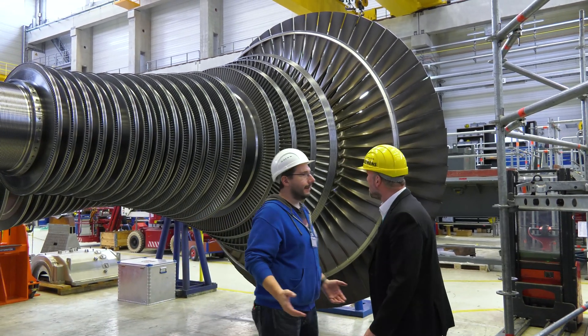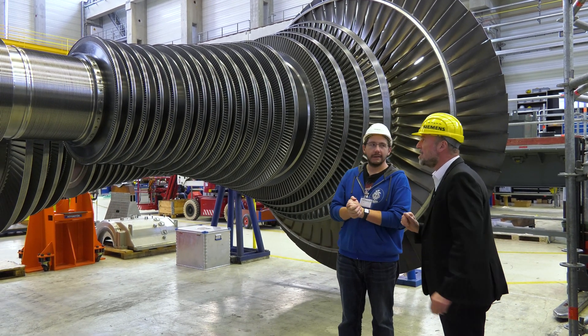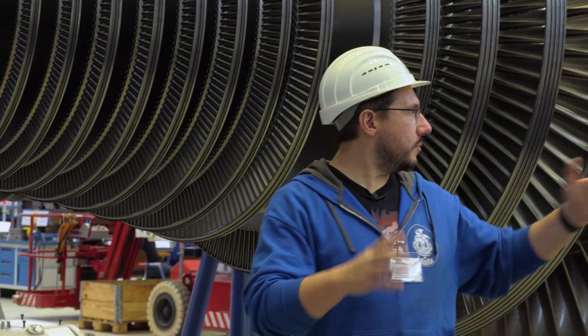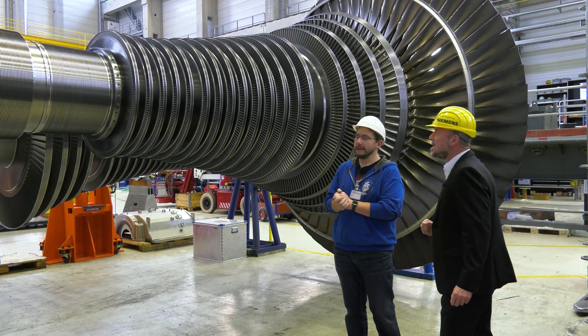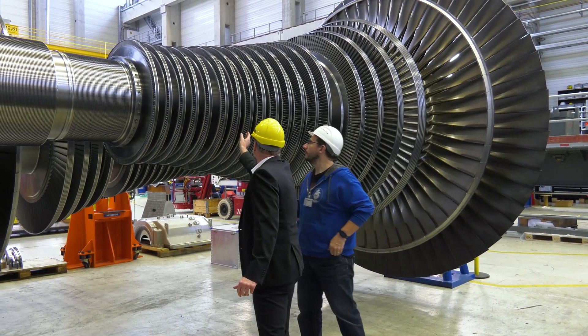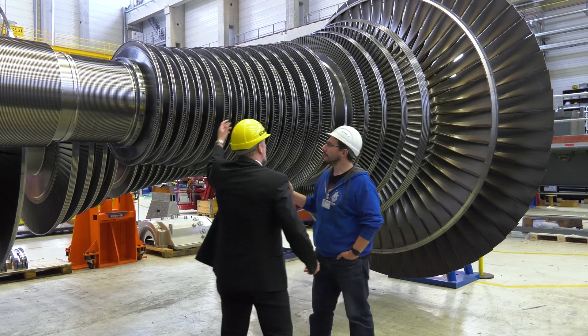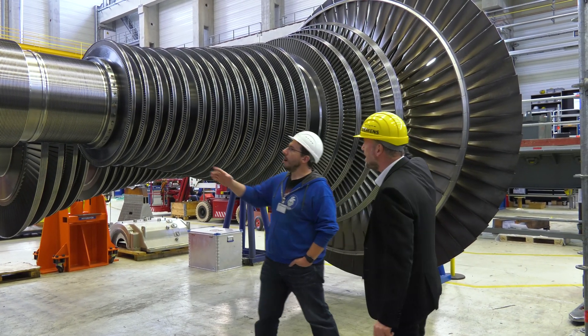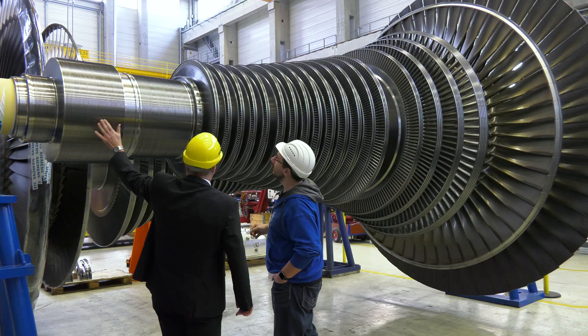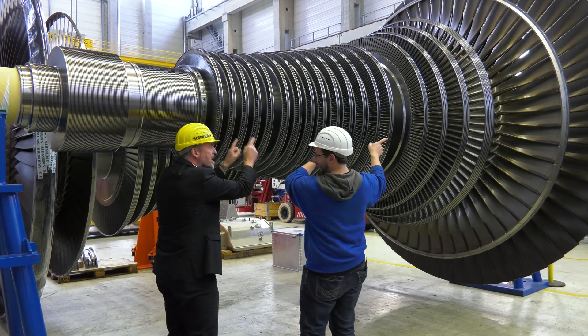In order to tell you how the steam turbine is built up — what you see here is the rotor of the steam turbine. That's the part which rotates and transfers the energy from the steam to mechanical energy. All the blades along this blade path interact with guide blades on the stationary part, and the steam will enter from here and drive the blades throughout the blade path up to the exhaust. These seals prevent steam from going the wrong way — we want the steam to perform work and go in the right direction.